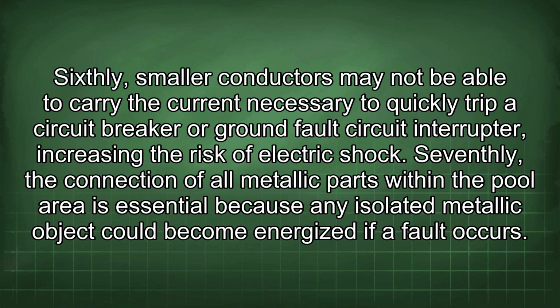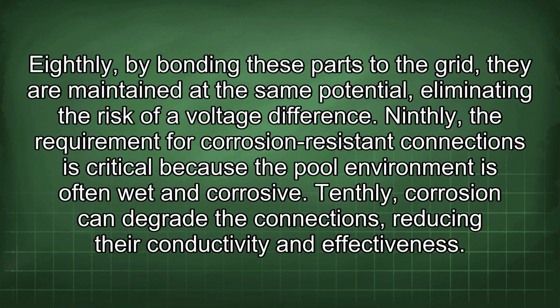Sixthly, smaller conductors may not be able to carry the current necessary to quickly trip a circuit breaker or ground fault circuit interrupter, increasing the risk of electric shock. Seventhly, the connection of all metallic parts within the pool area is essential because any isolated metallic object could become energized if a fault occurs. Eighthly, by bonding these parts to the grid, they are maintained at the same potential, eliminating the risk of a voltage difference. Ninthly, the requirement for corrosion-resistant connections is critical because the pool environment is often wet and corrosive.